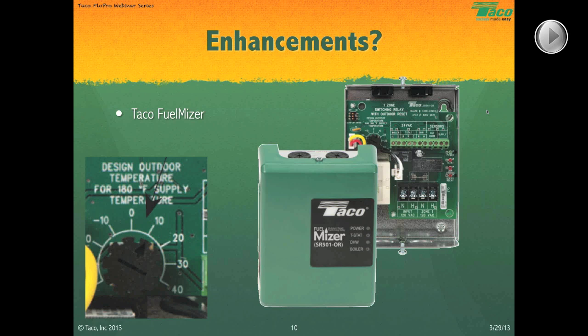So the zoning package has to go through the FuelMizer before it gets to the boiler. The FuelMizer says, all right, I understand you have a call for heat. Thank you very much. The boiler and I are going to figure this one out for you. You just go circulate whatever you have to do. The boiler and I are going to figure out what water temperature you need. And that's what the FuelMizer will do.